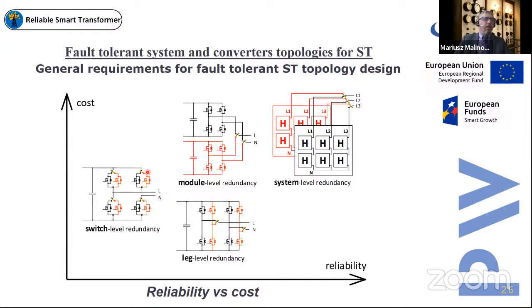We can find switch level redundancy, where series or parallel transistors are added to each module, but it's difficult from a design point of view, especially for high frequency converters, because we are currently considering the solid state transformer based on silicon carbide components. And due to the stray inductances and capacitances, it's difficult to do. Another option, which is shown here, is leg level redundancy, where an extra transistor leg is added to each module in order to allow reconfiguration. I think that this possibility is quite easy to realize.